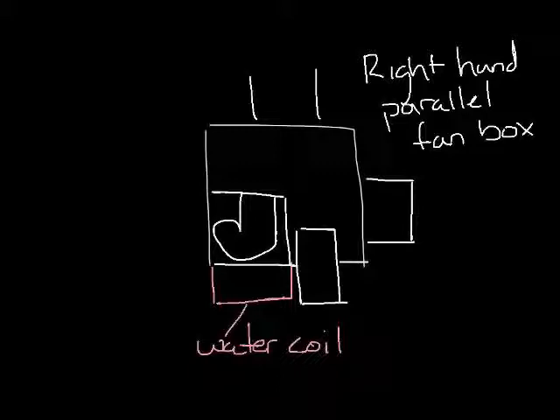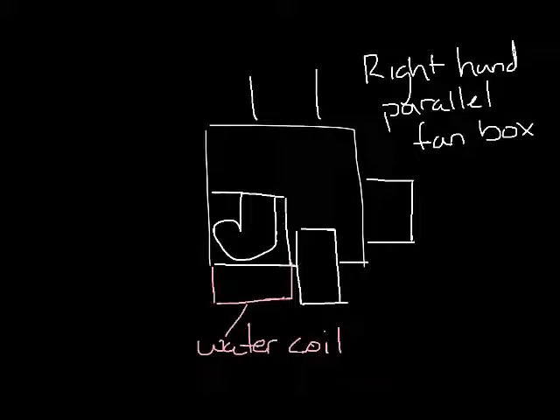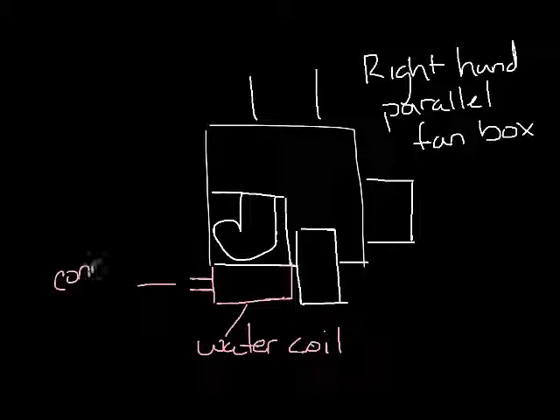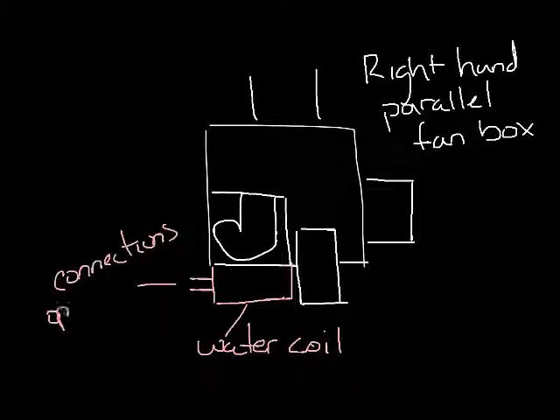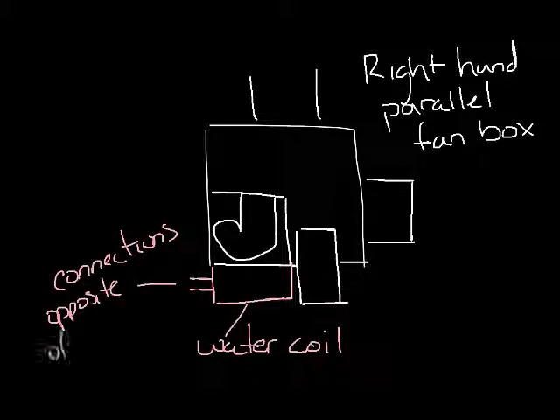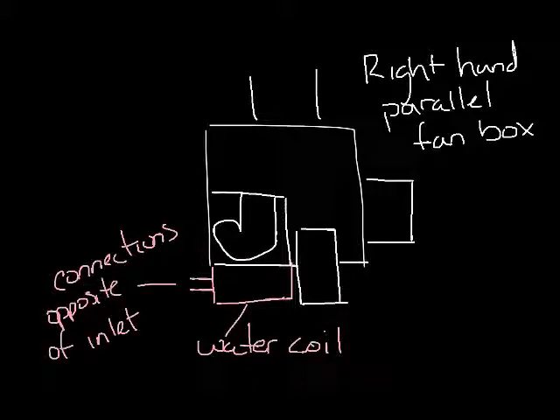But now you can see that you can't have a right hand box and right hand water coils because the connections would go directly into the primary air inlet. So on a parallel box with a water coil on the induced air inlet, it'll always have to have water coils with the opposite hand from that other box. In this case, a right hand box and left hand water coils.